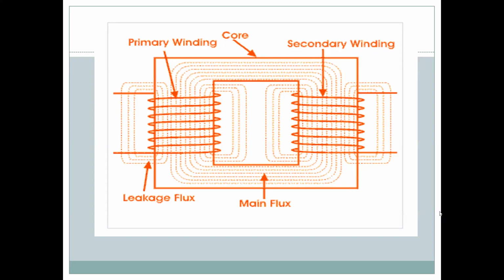It was something like 19% once upon a time. Now it has been reduced to 12%. But in the Western, developed world, it is in single digits, 6 to 7%. So all the energy generated from the powerhouse, to be transmitted to our place, to industry, gets lost in transmission. So we are not able to control those losses. So we are trying to control transformer losses, because the loading on transformers is not uniform. Sometimes it goes weaker, with no load loss, and during peak time it also consumes a lot of energy. So we always concentrate on this.